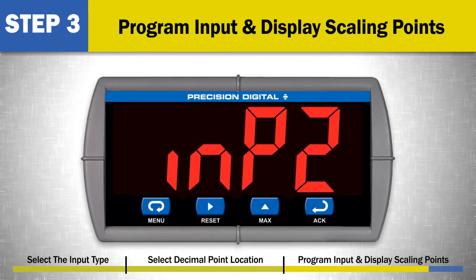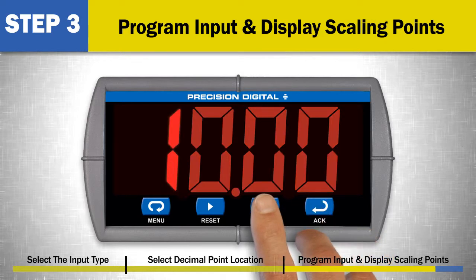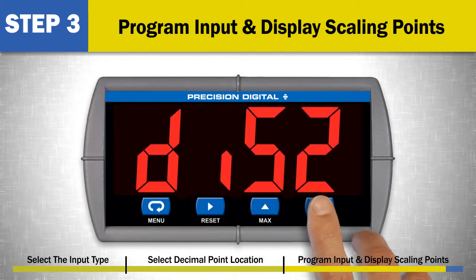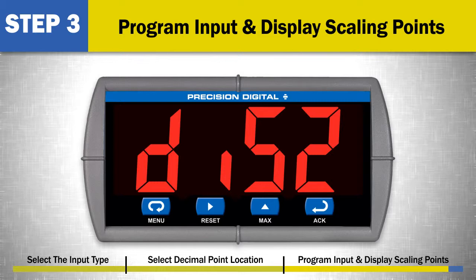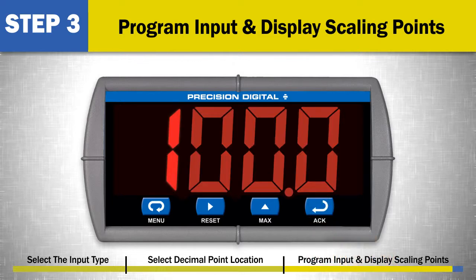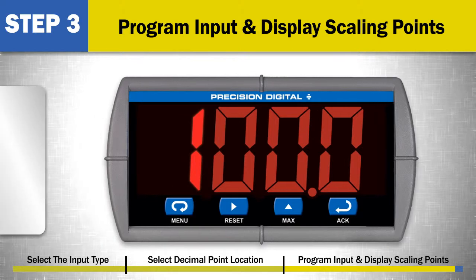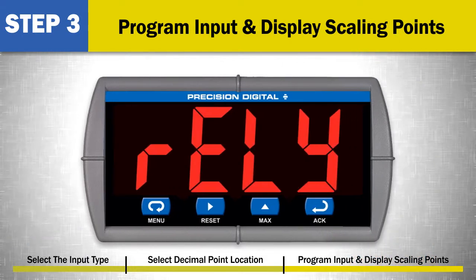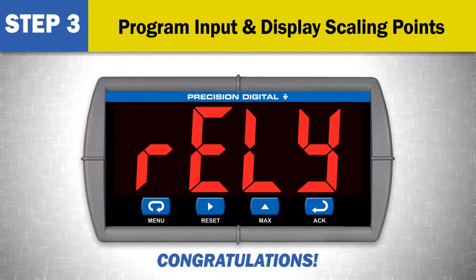Repeat these steps for input 2 and display 2. For example, to program a 0 to 10 volt input scaled to display 0 to 100, enter 10 for input 2 and its appropriate engineering units display value of 100 as display 2. When the display value for input 2 has been programmed, press the ACK button. Congratulations! You have just set up a 0 to 10 volt input and display scaling for your Precision Digital Meter.